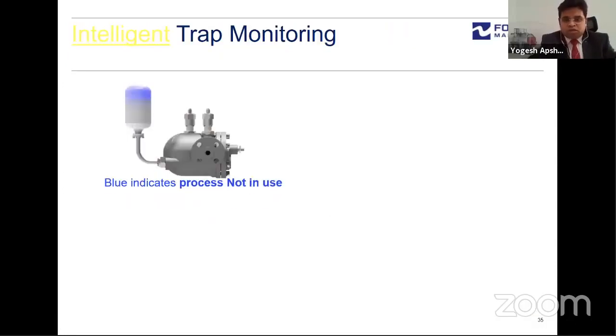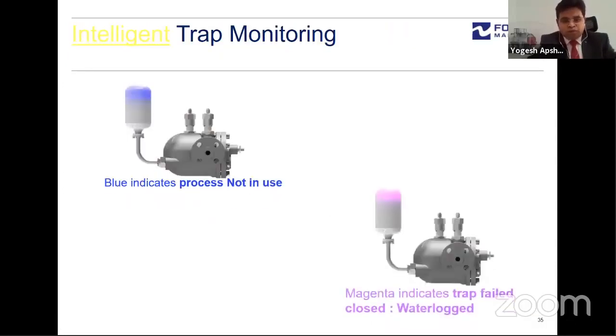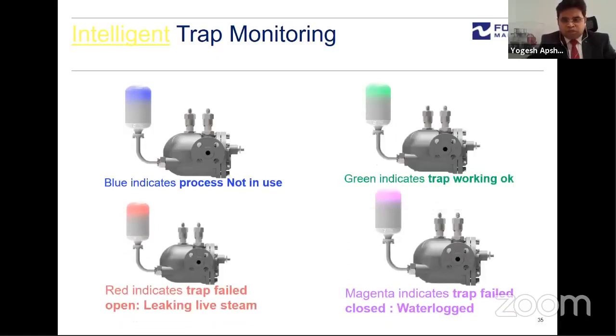I will run you through a small video which will show these different aspects of trap monitoring. What is intelligent trap monitoring? If there is a blue indication on the indicator, it means the process is not in operation and the steam is not used. If it is green, the trap is working. If it is red, it is leaking live steam. And if it is magenta, it indicates that the trap has failed and has waterlogged. You can observe that in the process. So let me take you through a one minute small video.